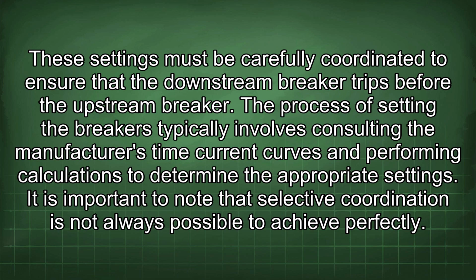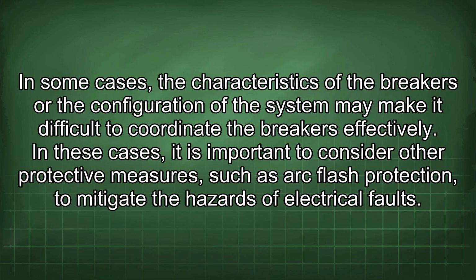These settings must be carefully coordinated to ensure that the downstream breaker trips before the upstream breaker. The process of setting the breakers typically involves consulting the manufacturer's time current curves and performing calculations to determine the appropriate settings. It is important to note that selective coordination is not always possible to achieve perfectly. In some cases, the characteristics of the breakers or the configuration of the system may make it difficult to coordinate the breakers effectively. In these cases, it is important to consider other protective measures, such as arc flash protection, to mitigate the hazards of electrical faults.